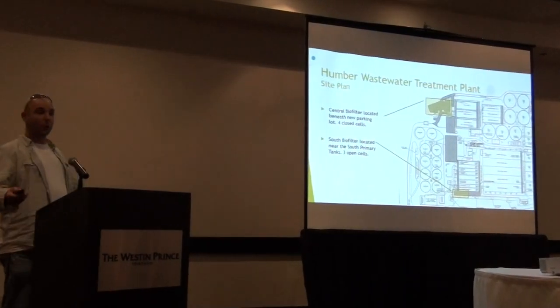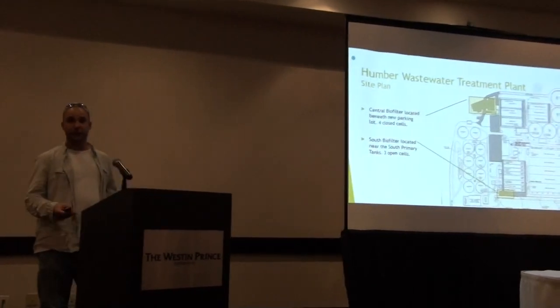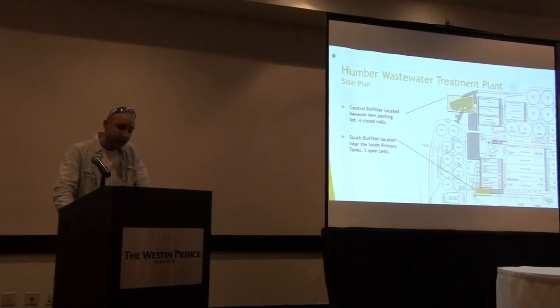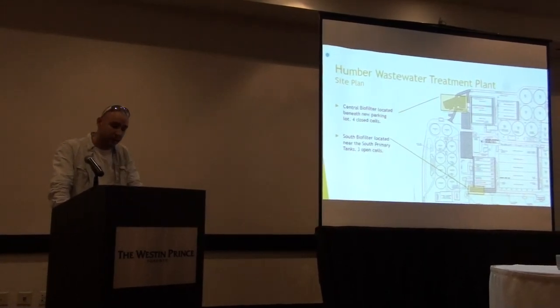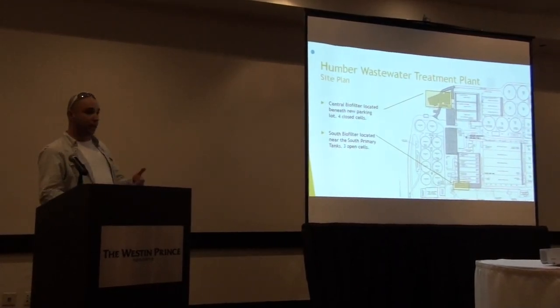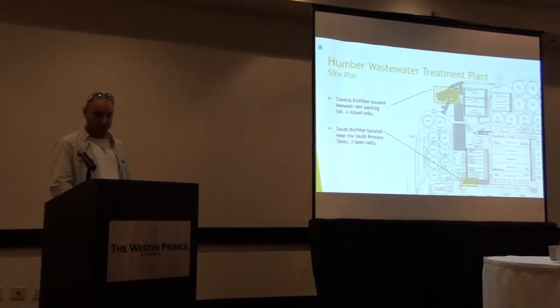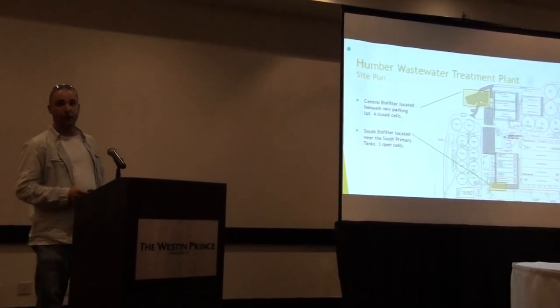So what is a biofilter, and how do they work? Essentially a biofilter is a giant living filter. We use it for odor control — in the air filtration process, what it's doing is taking microorganisms, and these things are treating the foul air that gets passed through, breaking down malodorous compounds, water-soluble VOCs, and sulfur compounds like H2S out of the air. The idea is that you have bacteria and fungus that become immobilized on a biofilm contained on a media. In this case the media is organic — it's wood chips, for lack of a better term. They basically degrade the pollutants coming through the foul air that's passed through.